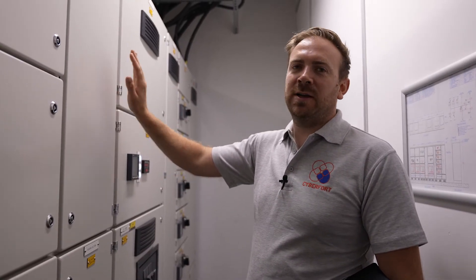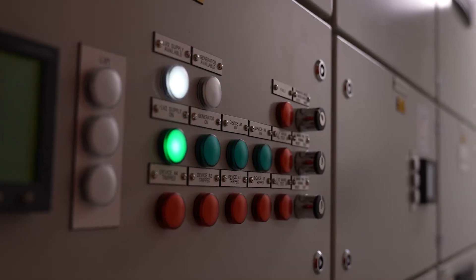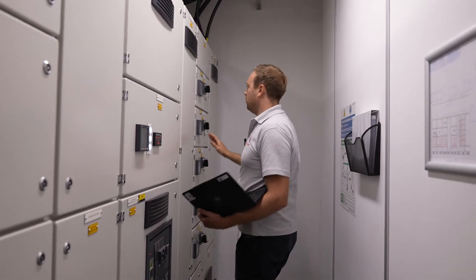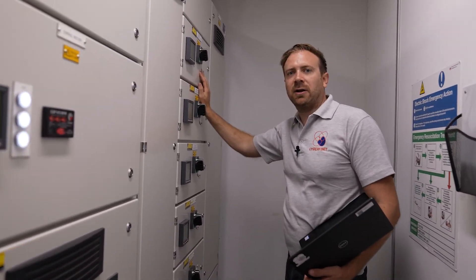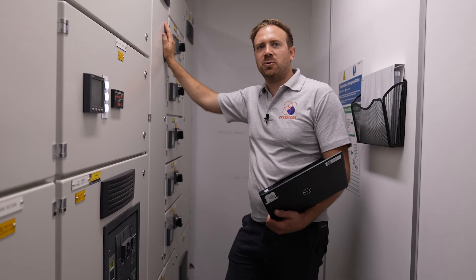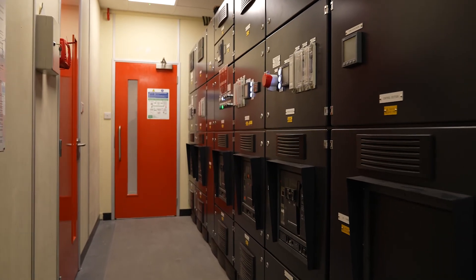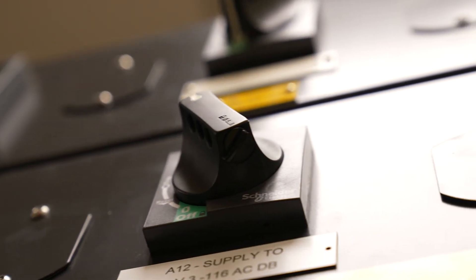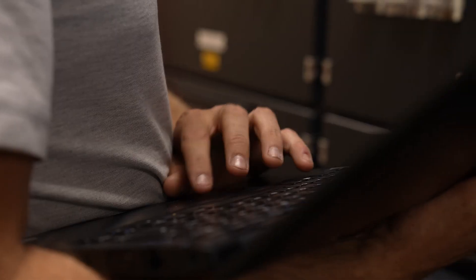Here we are in one of our LV plant rooms. This is one of our LV panels - we're going to take the meter readings straight from the source itself and input it into my computer. This is going to calculate our building load versus our IT load and calculate our power usage efficiency. Currently on this site we operate at about 1.36 PUE, which is pretty good. Here we are at our main switch panel, taking readings from the meter - this gives us our on-demand current. We then go into our BMS system to get the maximum on-demand current, input our figures onto a spreadsheet, and it calculates our PUE. That's what we've been up to today here at Cyberfort - hope you enjoyed the video, thanks for watching.